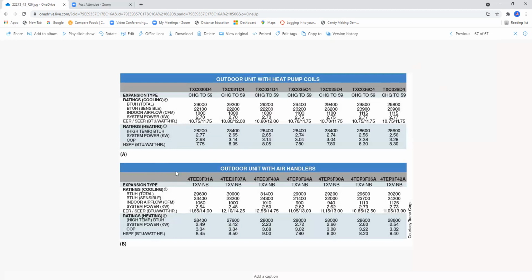Outdoor unit. The one thing you want to make sure when you are installing this equipment, more than anything else, you need to make sure that you have the right indoor coil matched to the outdoor section. Don't just rely on the guy behind the desk. He may or may not understand all this stuff. You need to look it up to see what the limitations are. You also need to do heat loss and heat gain calculations of the structure where you're putting in a heat pump. If you don't do this, you're going to come up short. It is as simple as that.